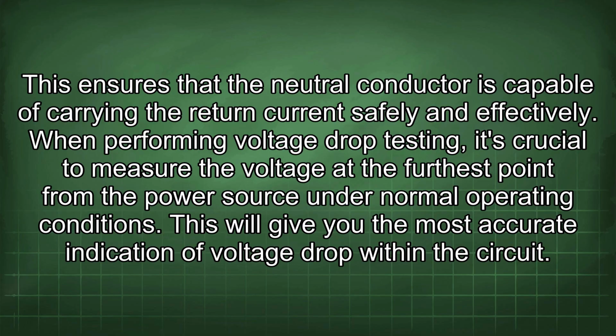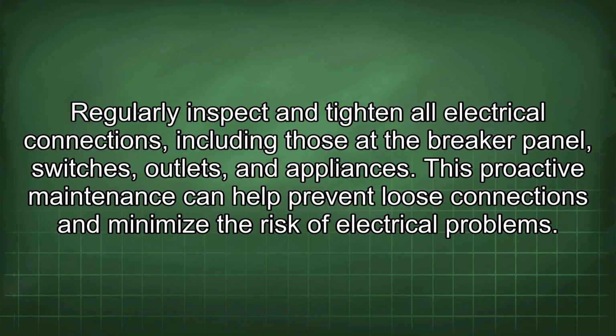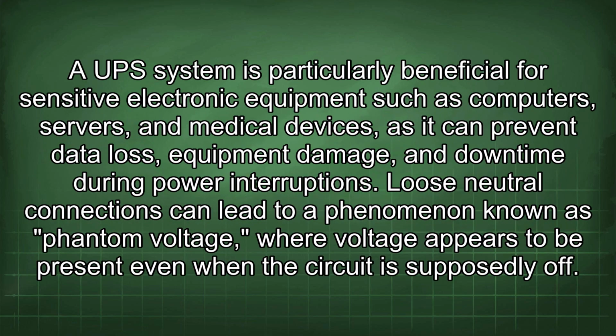When performing voltage drop testing, it's crucial to measure the voltage at the furthest point from the power source under normal operating conditions. This will give you the most accurate indication of voltage drop within the circuit. Regularly inspect and tighten all electrical connections, including those at the breaker panel, switches, outlets, and appliances. This proactive maintenance can help prevent loose connections and minimize the risk of electrical problems. A UPS system is particularly beneficial for sensitive electronic equipment such as computers, servers, and medical devices, as it can prevent data loss, equipment damage, and downtime during power interruptions.